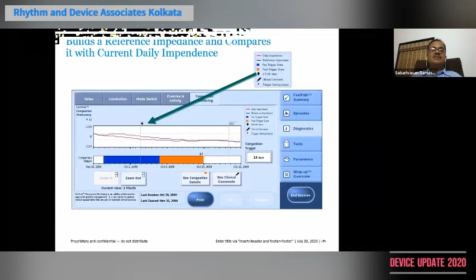So you will be having two lines. One will be an impedance line which is made as a reference, and this is the green line. And the red line or the pink line is the daily impedance. Over a 14-day period, it has collected a reference impedance and keeps that and compares it with the nominal impedance which is happening every day. And if the daily impedance is high, that means excellent. The body is having a lot of air and not fluid. Whenever the thoracic impedance is more, the lungs are clear. And whenever there is an impedance which is lower, it is always going to be a problem.